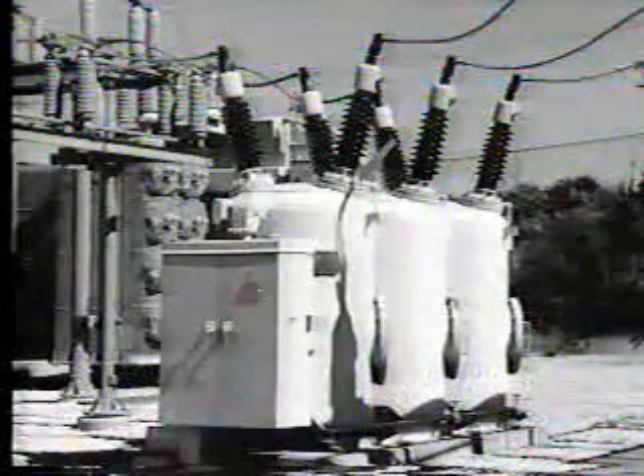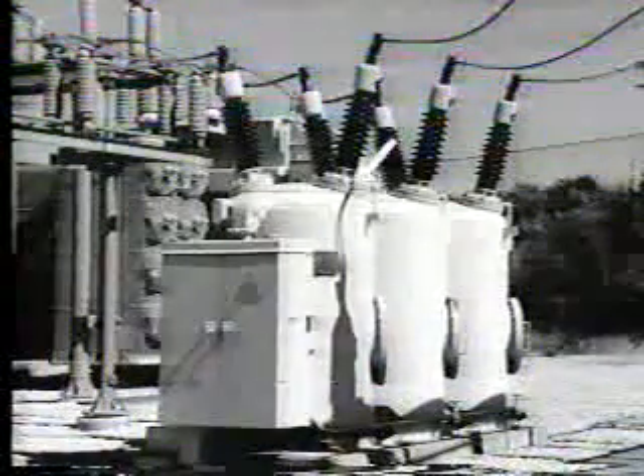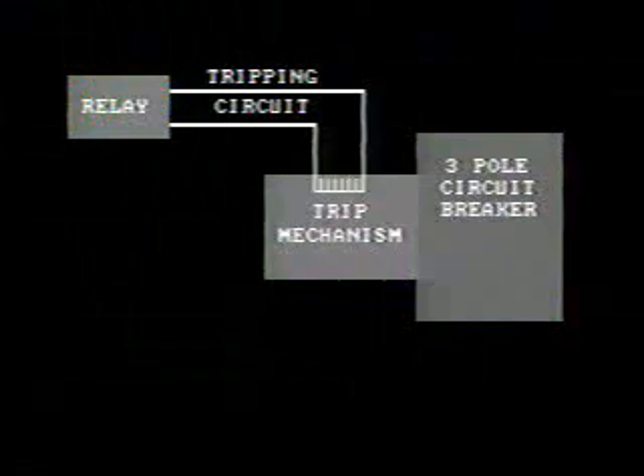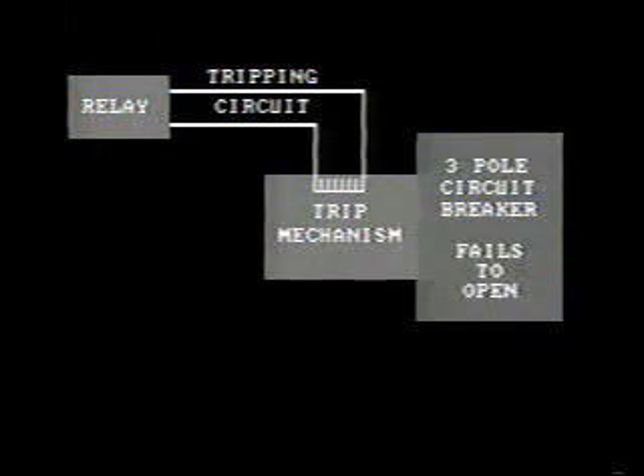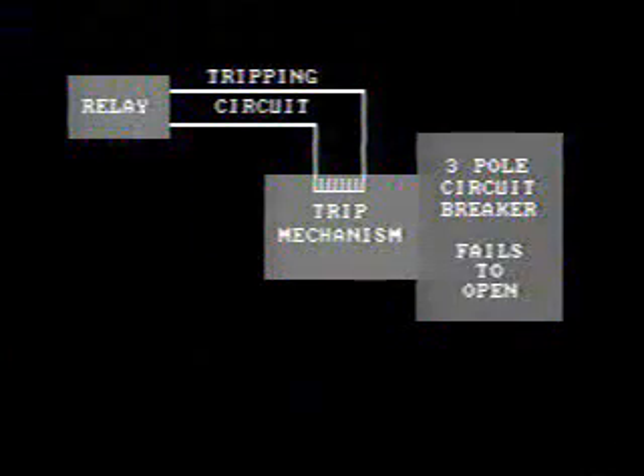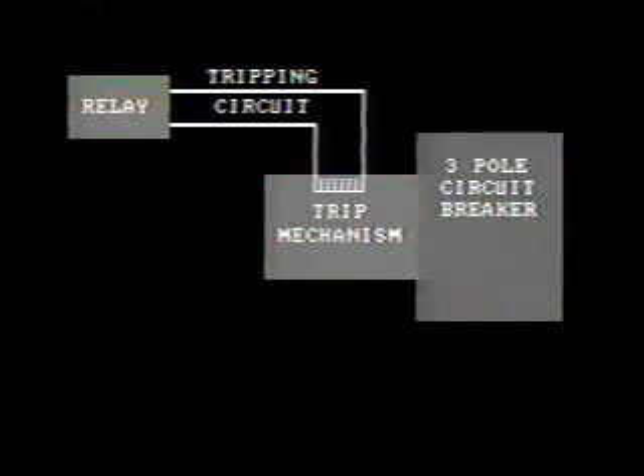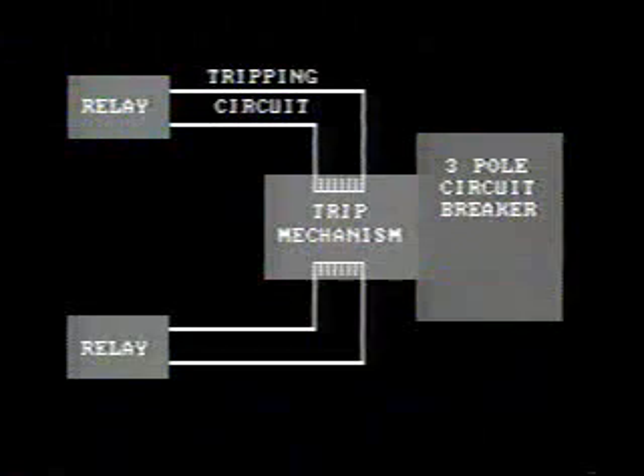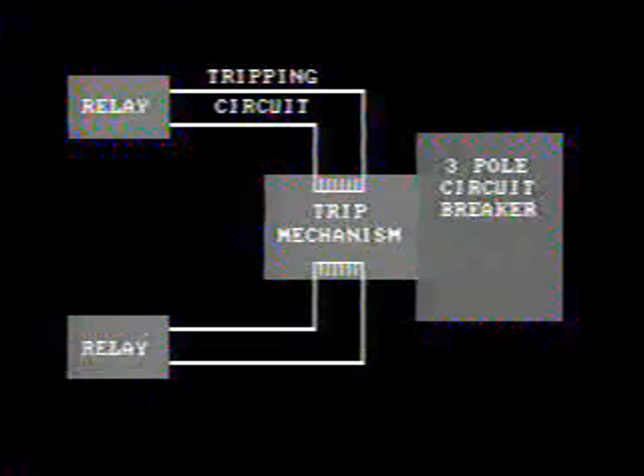Incidentally, current transformers are usually located in the bushings here. This type of breaker is usually provided with a single trip coil to operate the opening mechanism on all three phases. In rare incidences, a breaker may fail to open, perhaps due to a problem in the tripping circuit or in the mechanism itself. Indeed, as we shall see, this is one of the conditions that must be protected against. Where breaker operation is critical, an additional parallel tripping coil and circuit is often provided, fed from its own second set of relays.